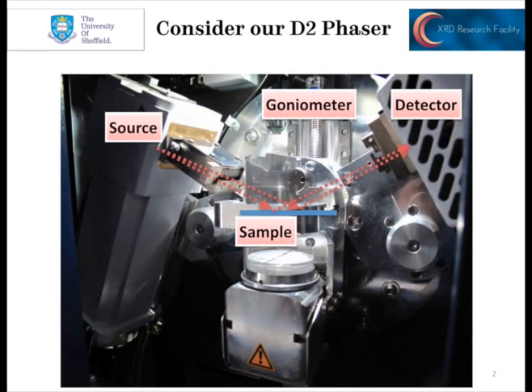The picture here shows the inside of our new instrument — looking into the chamber of the diffractometer. You can see on the left-hand side our X-ray source. This is firing a beam of X-rays onto the sample. The sample here is shown in the retracted lower position; normally during an experiment you have the sample diffracting X-rays up to the right into our X-ray detector. The whole central contraption, where all the gearing is, we tend to call a goniometer — sometimes a goniostat, but usually a goniometer.